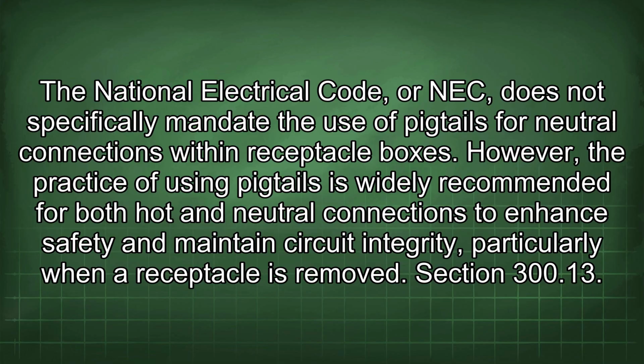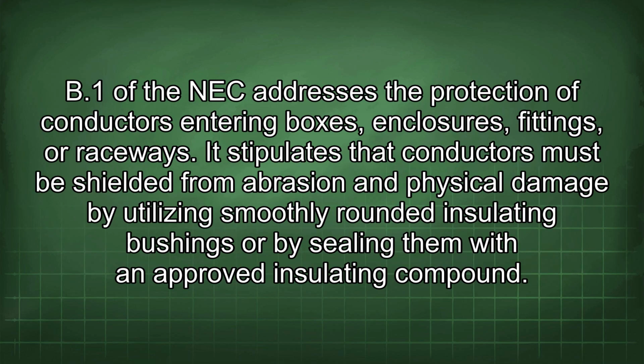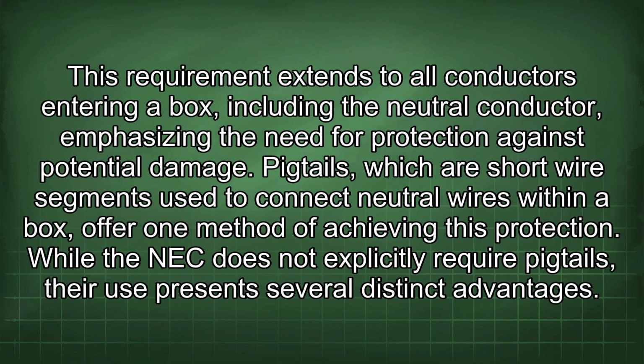Section 300.13 of the NEC addresses the protection of conductors entering boxes, enclosures, fittings, or raceways. It stipulates that conductors must be shielded from abrasion and physical damage by utilizing smoothly rounded insulating bushings or by sealing them with an approved insulating compound.